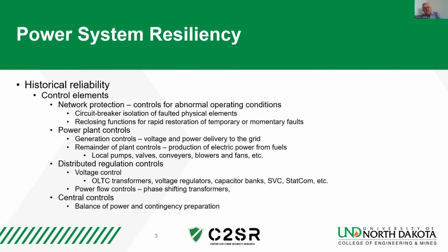When we have loops in the system, either transmission level or at the interconnection points, even in distribution, power flow control becomes necessary. And one of the primary tools we have is phase shifting transformers in the traditional sense, and flexible transmission lines with electronic components form the other component of that.